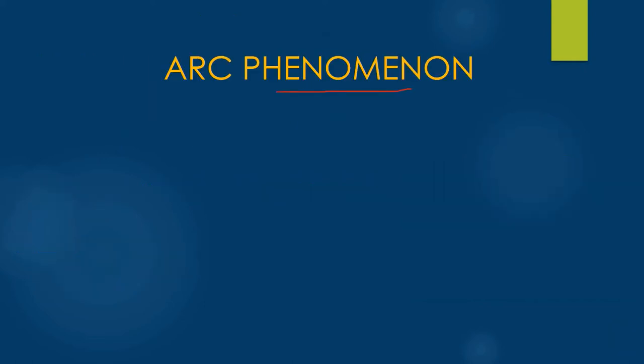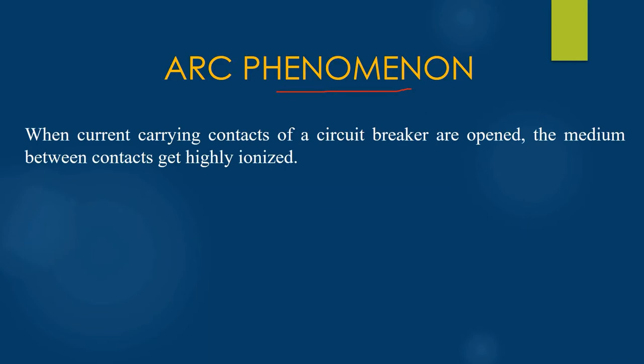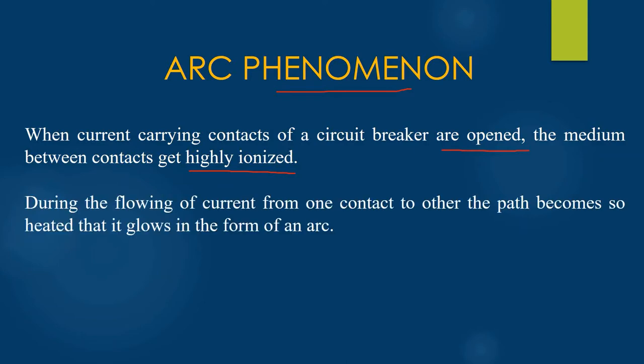Arc phenomena. When a fault occurs, the two contacts of the circuit breaker get separated from each other, and that's how the faulty current is interrupted from flowing into the system. But it's not that simple — when the two contacts of the circuit breaker are separated or opened, the medium between the two contacts gets highly ionized. When the two contacts are separated, the contact area between them decreases, which leads to increased current density and rise in temperature. This rise in temperature produces a large amount of heat, and therefore the low resistive part between the two contacts becomes so heated that it appears in the form of an arc.